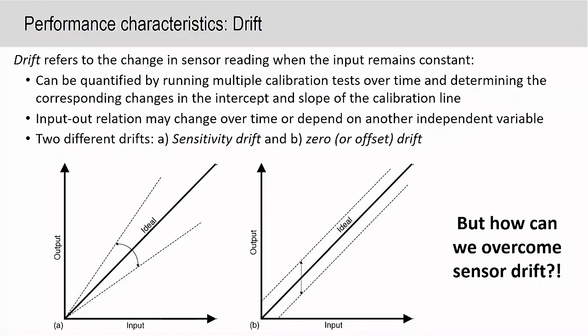You can also have other issues that lead to drift. That's something that we're currently working on. We're working on devices that are non-drift, or at least very, very low drift. But we also brought up calibration, which is another thing that can possibly be done. It's very hard when you're dealing with long-term implantable blood pressure sensors because calibration usually means putting a wire and a tube inside the patient's heart and vessels, which is not always so easy.